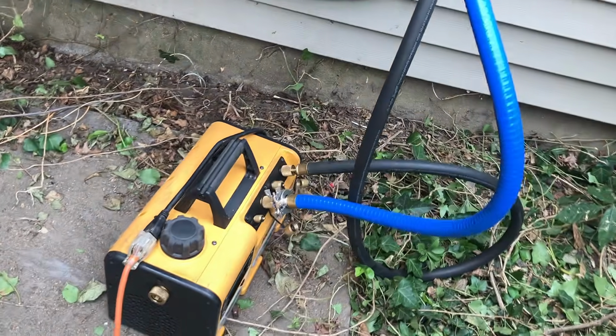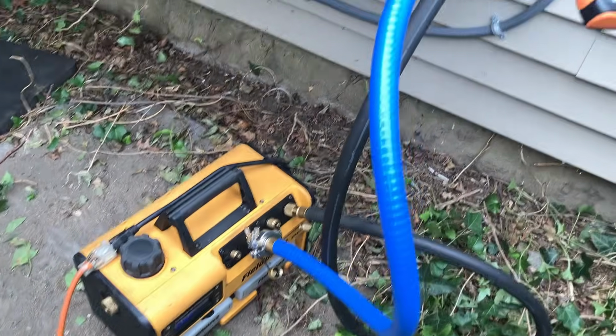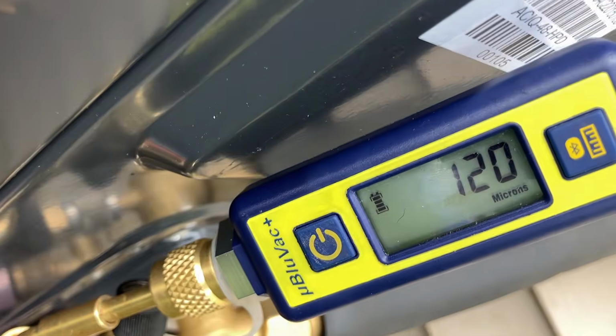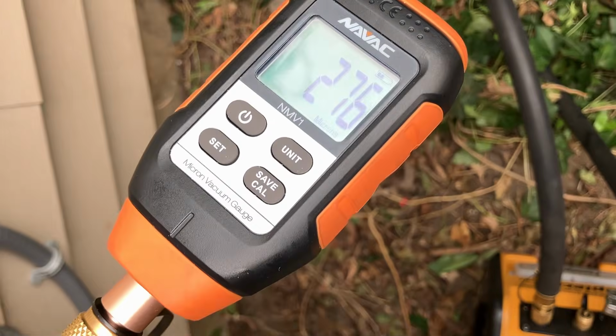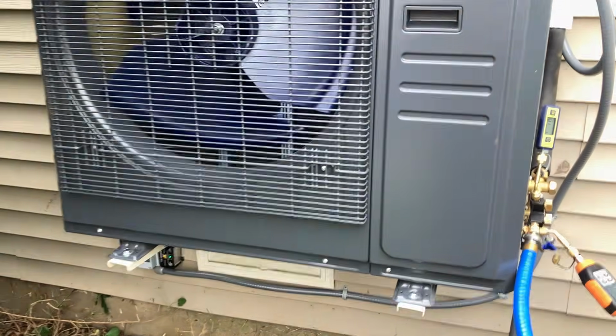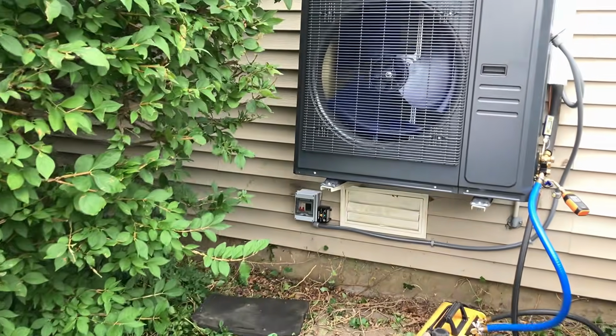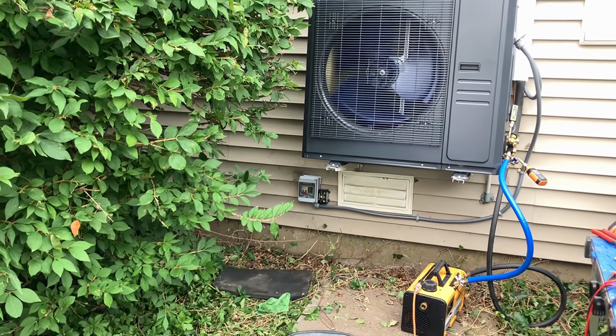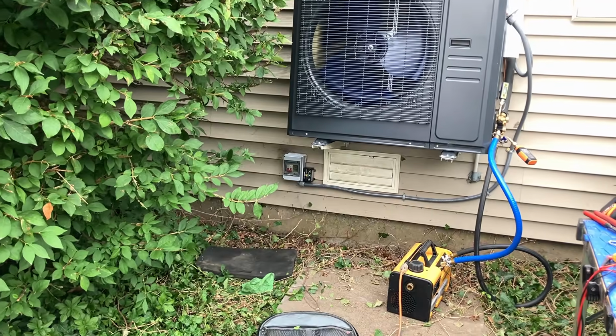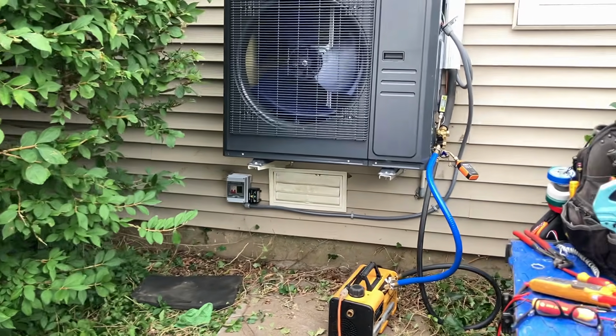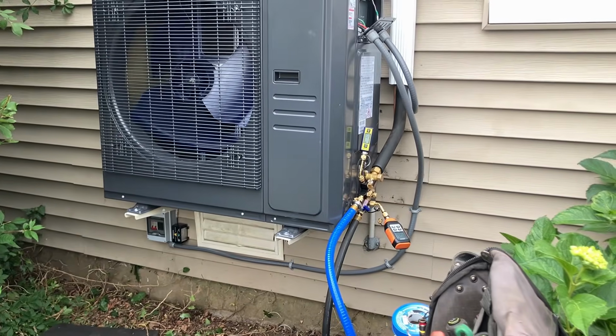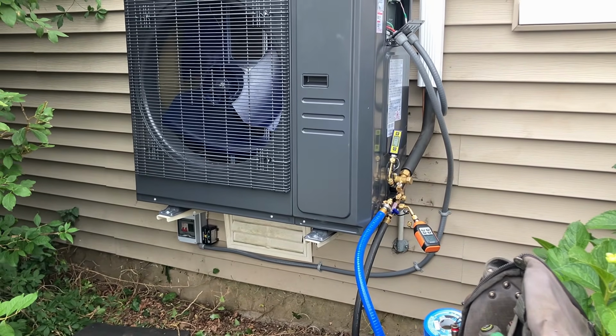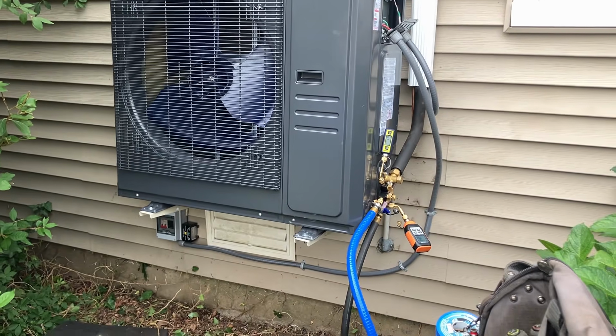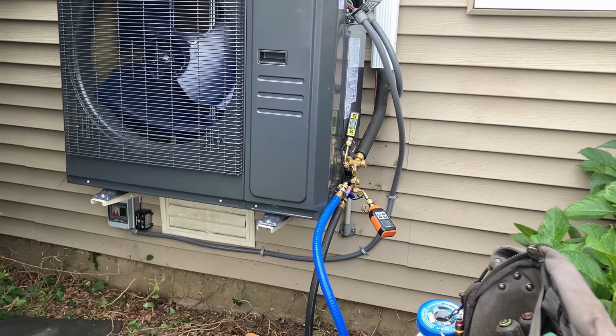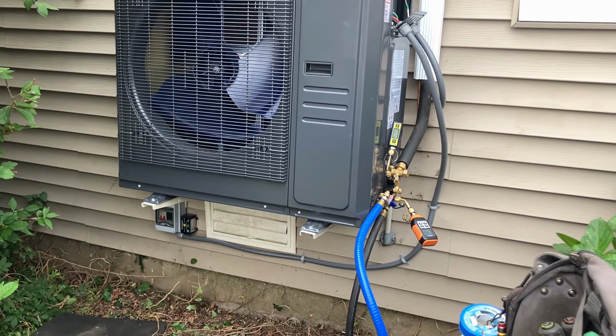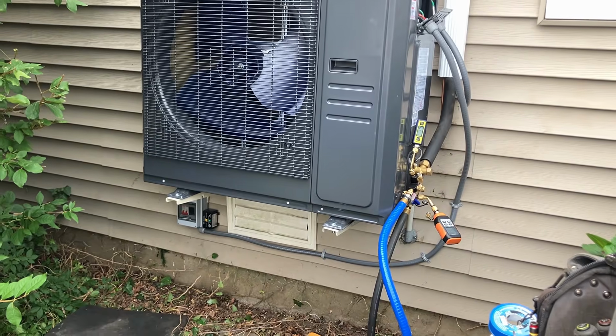And that's why we hook up a high quality vacuum pump and pull this system into a deep vacuum, measured in microns, not PSI. My goal is always to see that micron gauge drop nice and low, and more importantly, hold after I isolate the system. That tells me there's no leak and no moisture left boiling off inside the piping. Because that's what happens: when you're pulling into negative pressure in a vacuum, any moisture in the system is going to boil off, steam off, and expand. That's why sometimes you see the micron gauge jump up and then back down again, because it's boiling off that moisture, which expands like 20,000 times its mass.